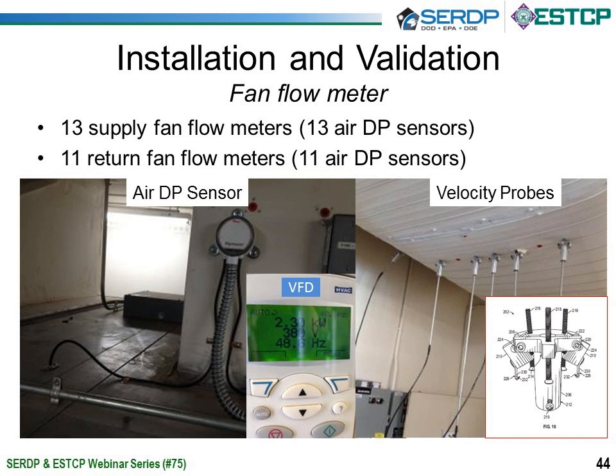We temporarily install velocity probes across the cross-section of that duct and make velocity measurements that allow us then to calculate the flow rate through that duct. The inset on the lower right-hand side is a mounting bracket for the probes that make these measurements, and this enables us to install the probes entirely from the outside of the duct.